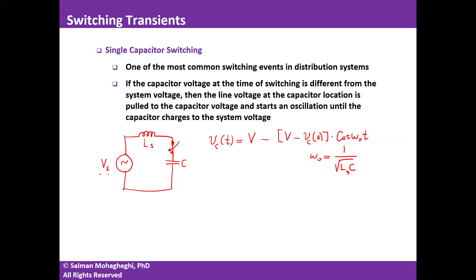Despite the fact that the voltage is a sinusoid at 60 Hz, I'm considering it a constant value. The magnitude of oscillations is essentially the difference between the system voltage at the moment of switching and the initial voltage of the capacitor. If the capacitor is switched on at the moment the system voltage equals the voltage across its terminals, we won't see any transients. When contact is made, the capacitor pulls the system voltage to its own initial voltage V_C0, and then starts an oscillation around that point.